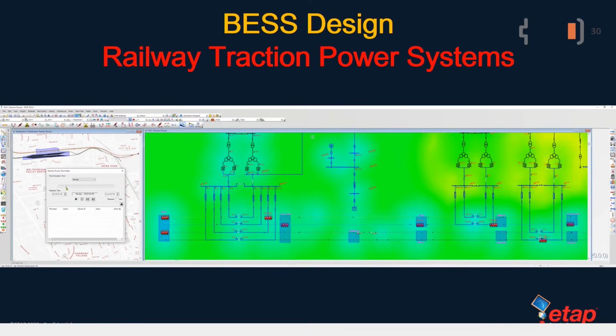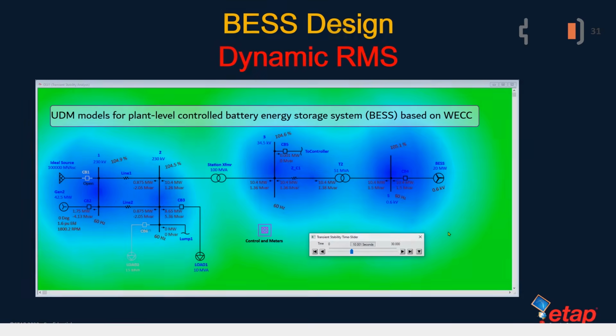So far, we've been looking at steady state analysis such as power flow, unified power flow, and DC short circuit. Let's turn our attention now to the dynamic side and observe a few examples related to dynamic RMS. In ETAP, you can model the dynamics of battery energy storage systems together with their controller using UDM. ETAP already includes UDM models for plant level control and also includes WECC battery energy storage models. So let's take an example where we've utilized the WECC battery energy storage models along with the plant level control and run a few simulations and observe the transient behavior of battery energy storage systems in ETAP software.